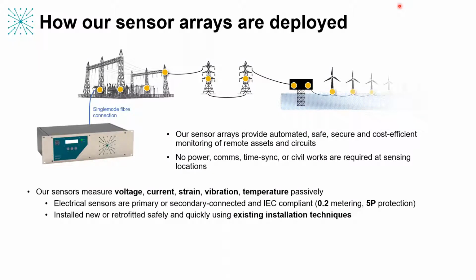The key thing for electrical engineers here is that the electrical sensors that we provide are IEC compliant for 0.2 metering or 5P protection. And the timeliness of the whole system operates within the timescales for IEC 61850. So what this means is that from a single platform, you can do protection functions, you can trip breakers, but you can also derive from that same data and from those same measurement locations, without duplicating anything, your power quality, your synchrophasors, and you can start to look at correlations between the electrical system and the mechanical system.